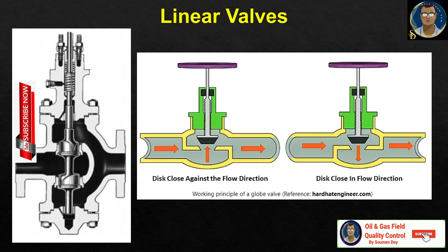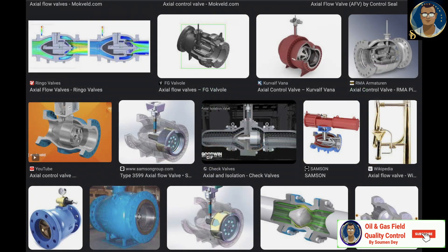Linear valves come in two types: multi-turn and axial. Both rely on the linear motion of the flow obstructor but differ in construction and operation. Multi-turn rising stem valves move the obstructor by rotating a threaded rod, also called the stem, which is attached to the obstructor. These are mostly used for flow control applications. Axial valves use pneumatic and electromagnetic force to slide the obstructor along the axis. Co-axial valves and angle seat valves are examples of axial valves.